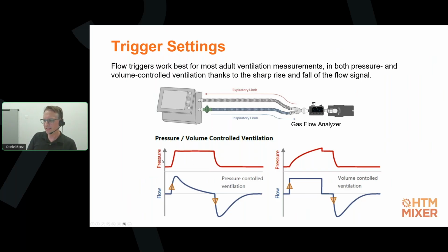And this means that we will have signals. Typically with ventilators, you will hear the terms volume controlled and pressure controlled ventilation. So it's not that important to understand these details, but the key is, in both these different modes of ventilation, your flow waveform will typically have these steep rising and falling edges we are looking for at the start and the end of an inspiration phase.